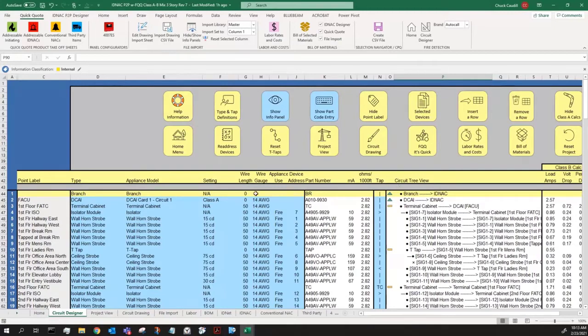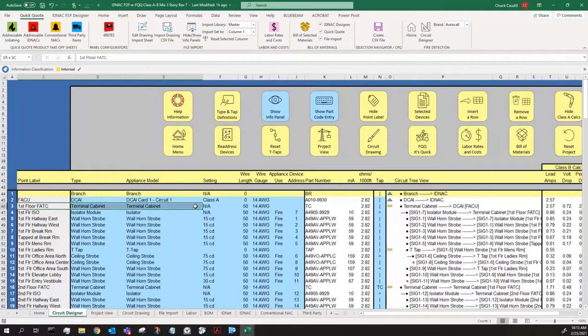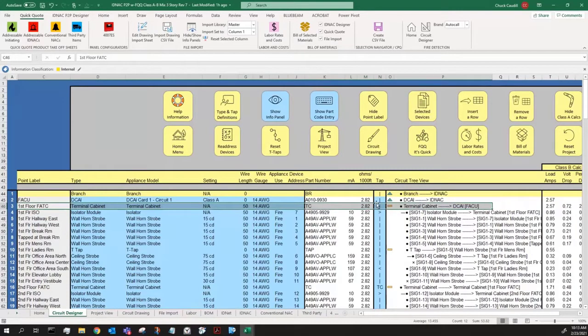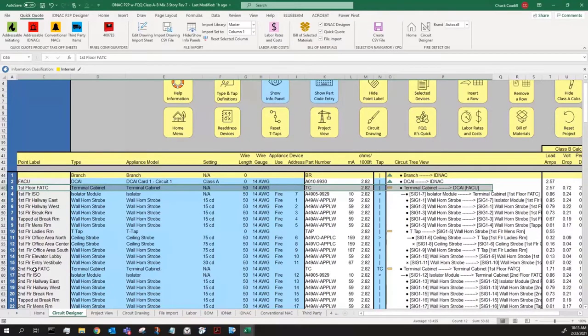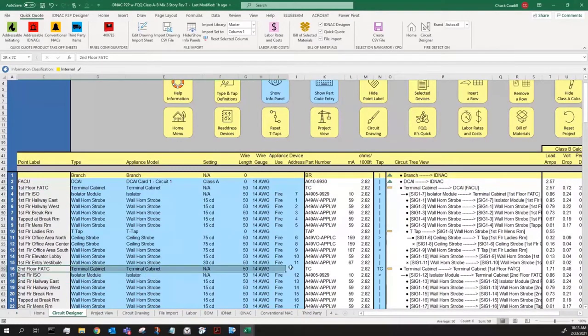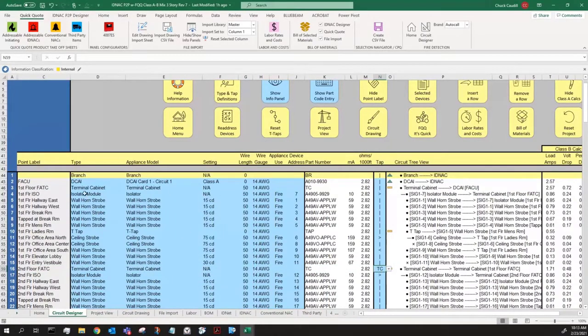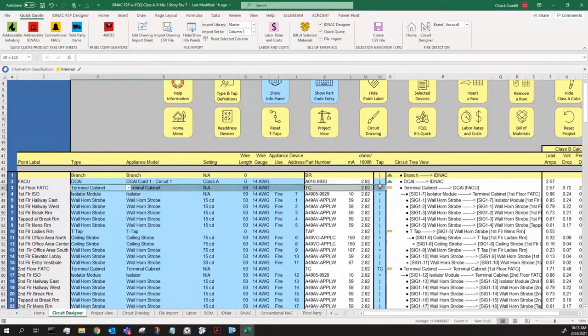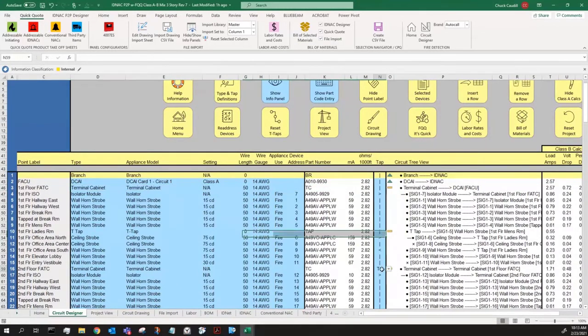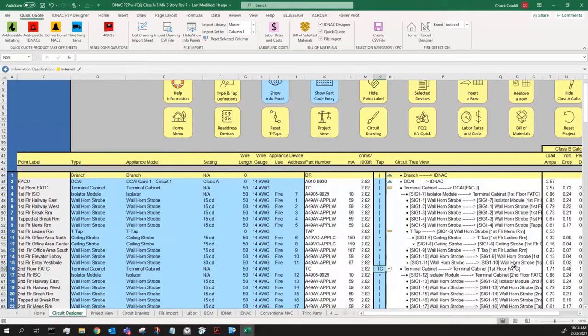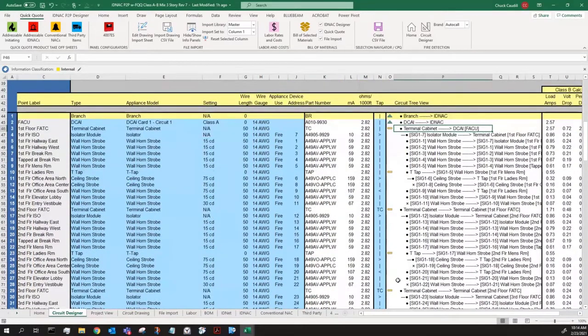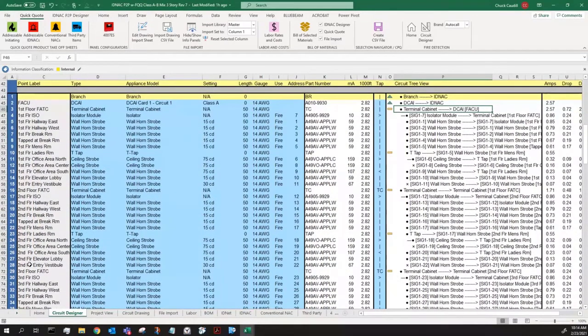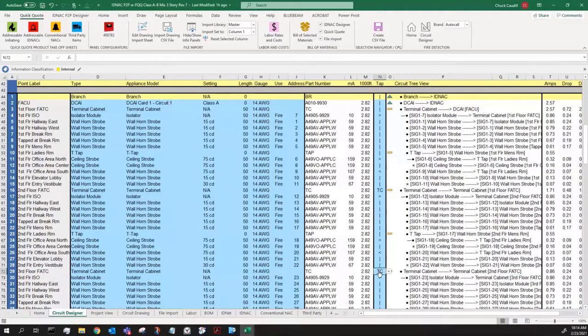So how do I do that? The first thing I start with is a DCAI, like we did previously. And my first device is going to be a terminal cabinet for the first floor, and it's direct connected to the DCAI. The next lines you see are my field wires. We're going to come back to that. But let's go to the second floor terminal cabinet, FATC terminal cabinet. And I'm telling it TC. I want the sheet to scan up the page and find the next terminal cabinet above me, which is here. So I put some alphas in here. What this does, it helps me a little bit over in this right-hand column. This TC terminal cabinet ties to the terminal cabinet on the first floor, which is up here. I do the same thing with the third floor terminal cabinet. Third floor FATC ties to the second floor FATC, because I said TC here.